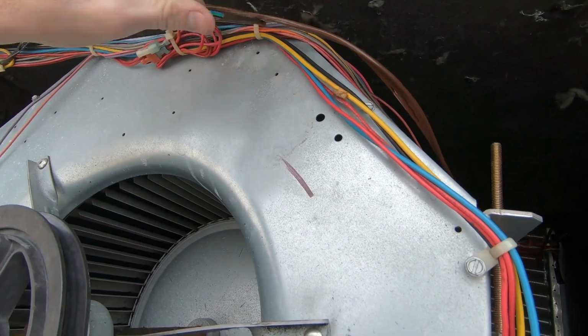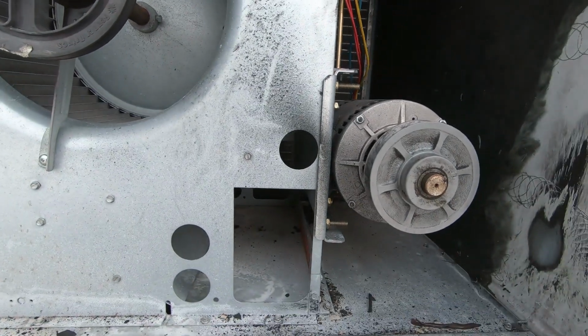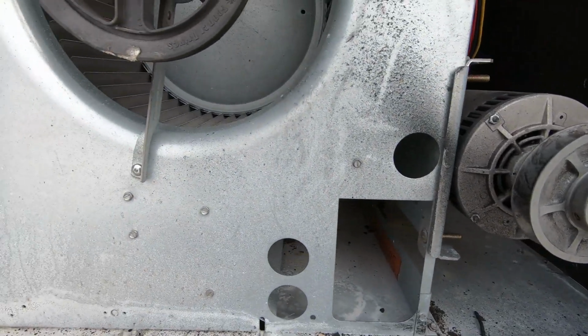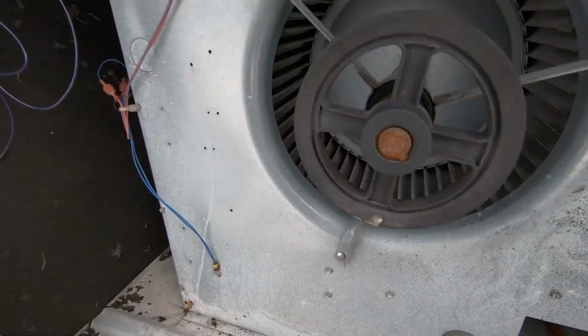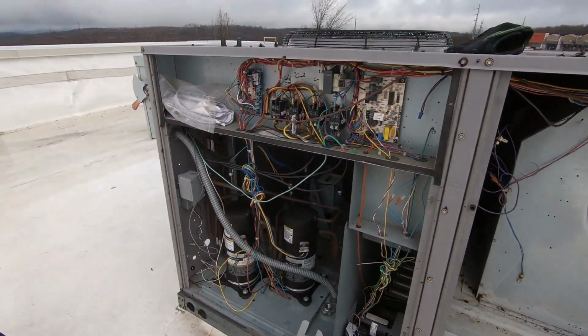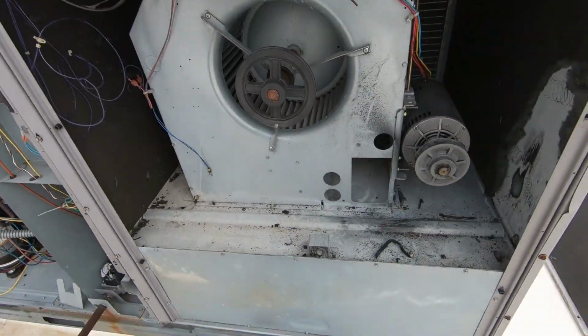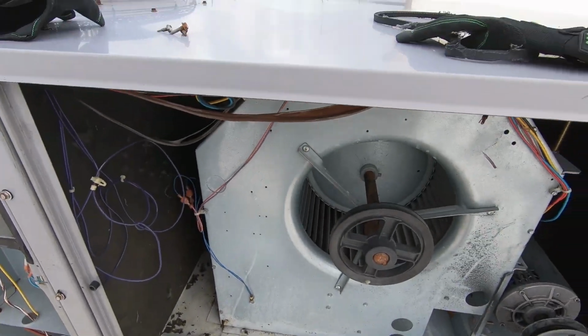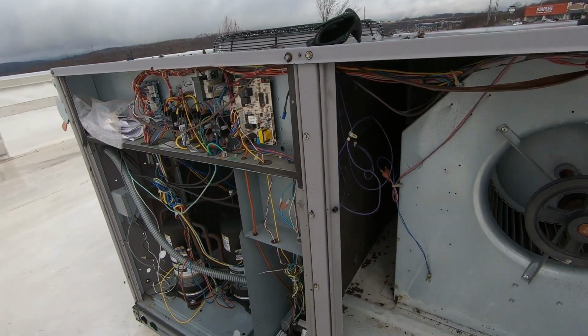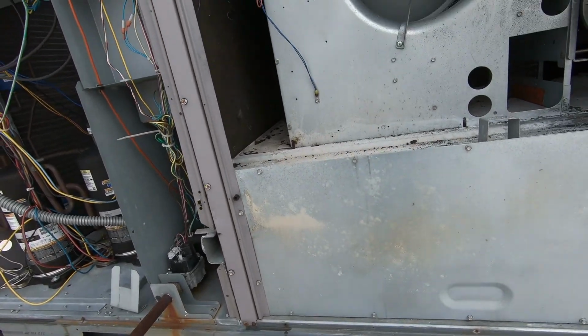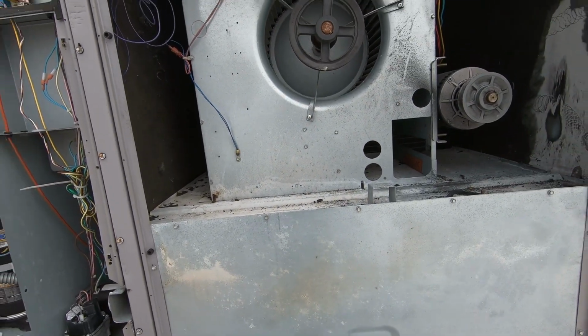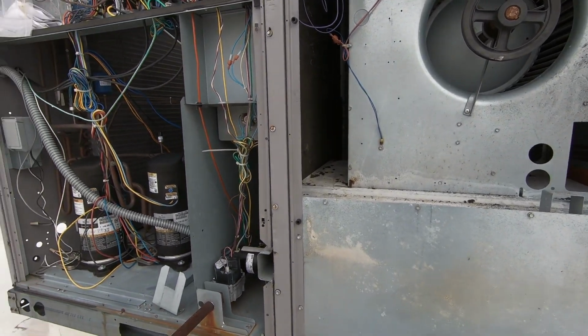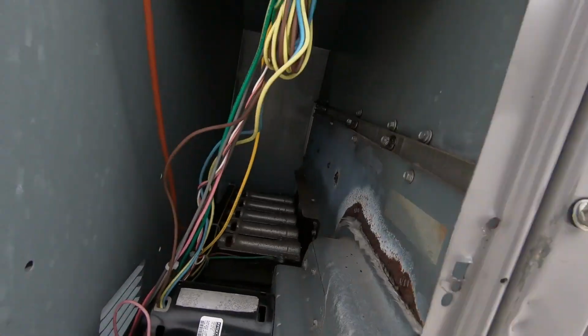Was there a fire or a heat exchanger? I mean, you'd think the safety would kick it off. I'm gonna pull this heat exchanger inspection cover. We're gonna take a peek, because if the heat exchanger's cracked as well, they're just gonna get a blower motor and a heat exchanger replacement.